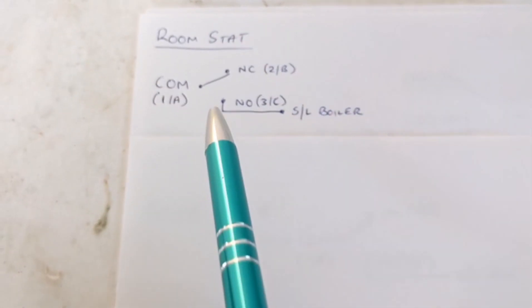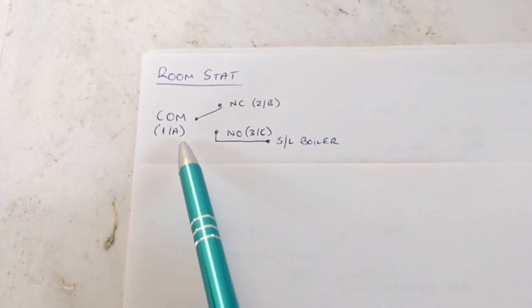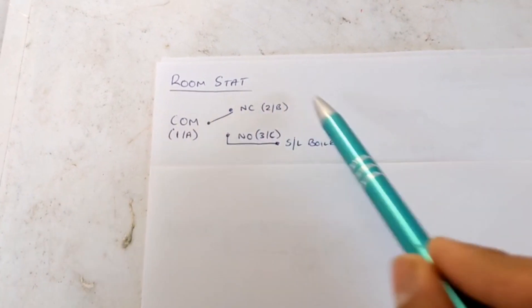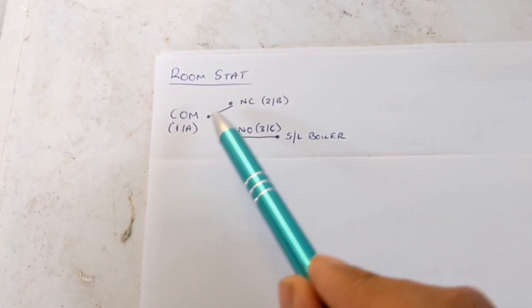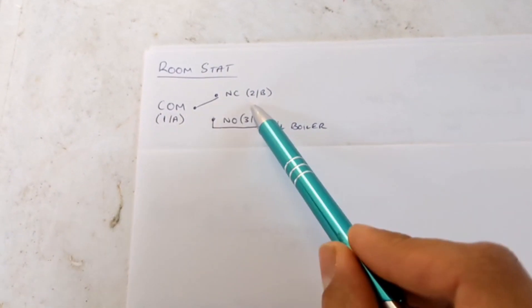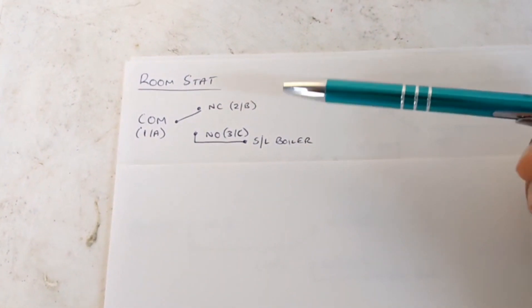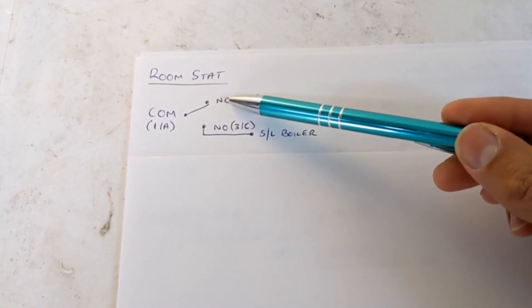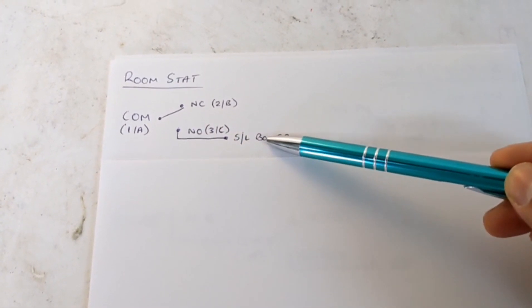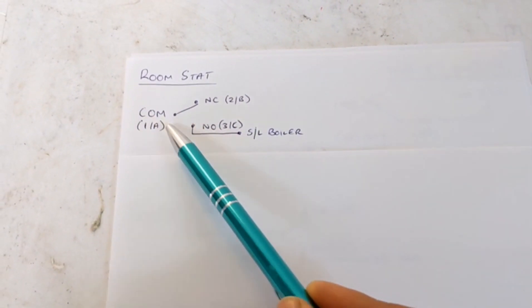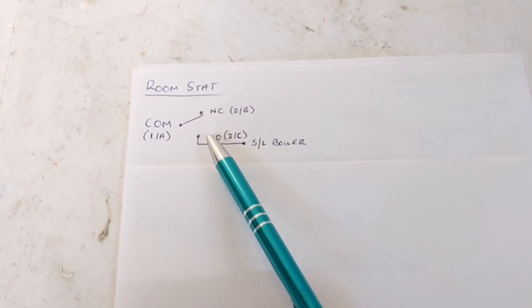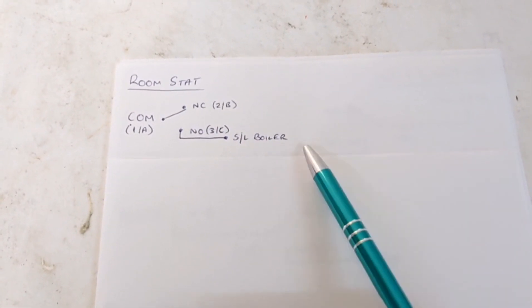Basic room stat wiring: you're going to have three terminals — this could be a mechanical room stat or a wireless receiver for a wireless room stat. You're going to have common, normally closed, and normally open. This could also be labeled as one, two, three or A, B, and C. The easiest way to remember this is NO spelt backwards is ON, so that's your switch live to the boiler. You should have 240 volts on your common, and when there's a demand for heat that will switch over to normally open and send power down to the boiler to fire it up.